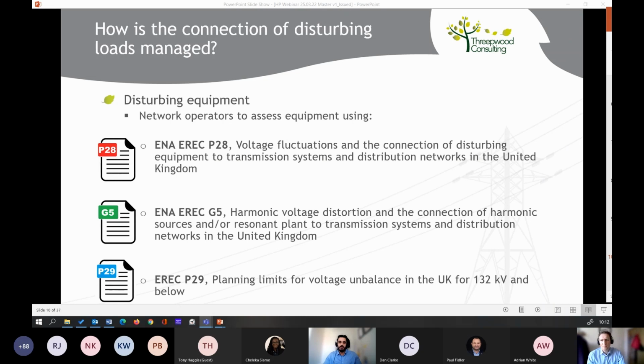Similarly, we've got G5, which is for harmonics. Again, you have 3 stages within G5. Depending on the harmonic emissions, the equipment can either be connect and notify, where you connect the heat pump and notify the DNO that it's been connected, or the DNO needs to do some assessments and studies to make sure that the heat pump will not cause any disturbance to the network. And finally, P29. Oh, excellent. I guess it's P28 and G5 which are most applicable in the case of heat pumps.